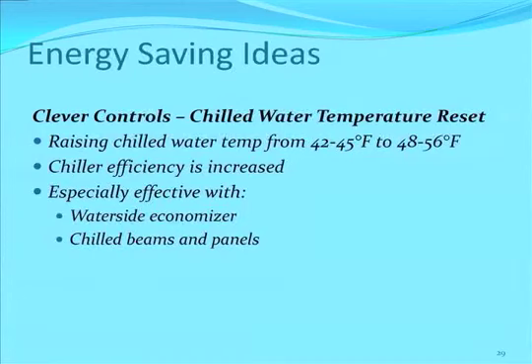Resetting temperatures as far as the operation of your chiller. A lot of chillers are designed for peak operation, peak chilling capacity, which is a very small portion of the year. Most of the time, you're under peak loading. During those times, you may be able to raise the chilled water temperature, get the cooling that you need in the space for thermal comfort, and your chiller won't have to fight as hard. So if you raise that chilled water temperature, its efficiency is improved.